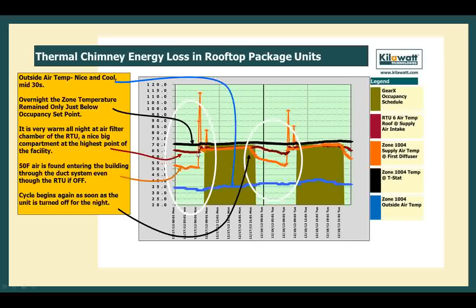The only point where this heat could be coming from is from the interior of the building. So we then took a bunch of U12s down and stuck them into the diffusers inside the building and the ductwork. And lo and behold, what we found is that entering the building during unoccupied hours was about 50-degree air. Exiting the building during unoccupied hours was 65-degree air. The only place the hot air came from was inside. The only place the cold air came from was outside. As soon as the mechanical systems were turned on, everything stabilized throughout the day. As soon as the mechanical systems were turned off, once again, there was cold air rushing into the building. What we have determined was happening was that the dampers used to seal or supposedly seal off the duct system are either broken, not working, or may not have even actually been installed.